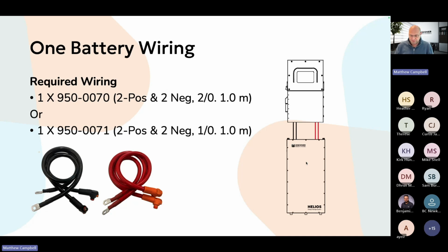I've got some part numbers here, and we'll make these slides available so you can take note of them. There are 2 wiring kits for this installation, either 1-aught or 2-aught, so you get to choose. They come with connectors on one end and a ring terminal on an M8 size, which is what Sol-Ark requested, or their specification, on the 15K and all their inverters. All you'd need is one set of either the 2-aught or the 1-aught. They come with 2 sets of cables in each, so 2 positive and 2 negative, making for a very quick install.